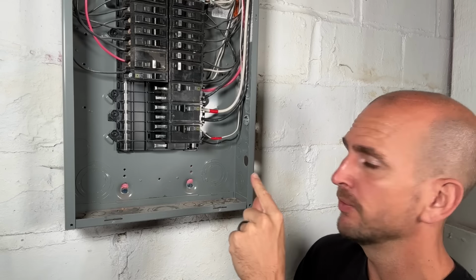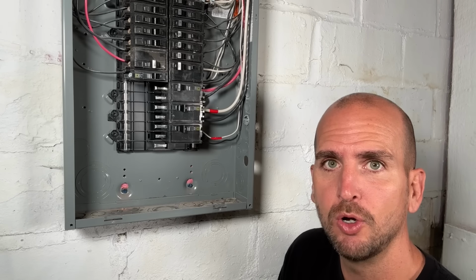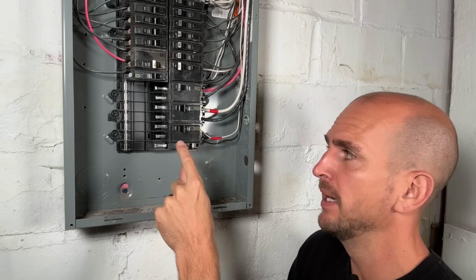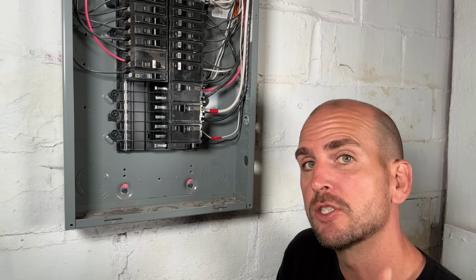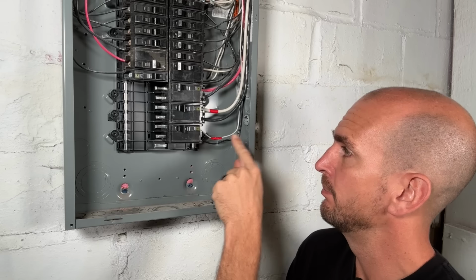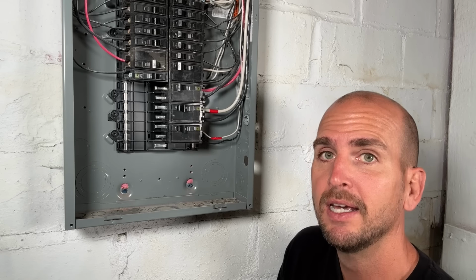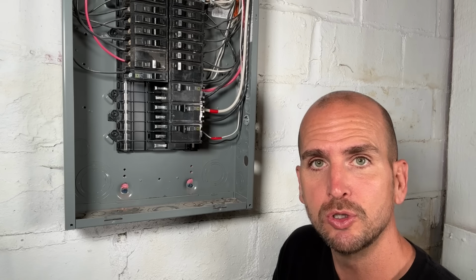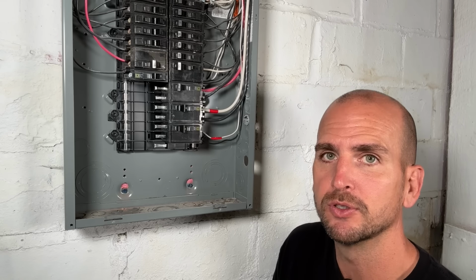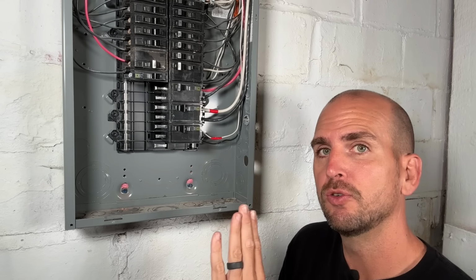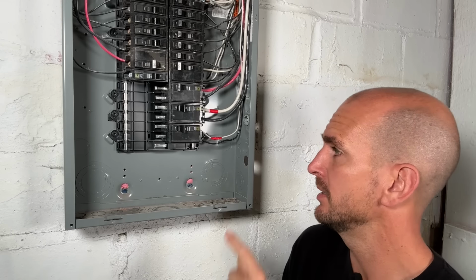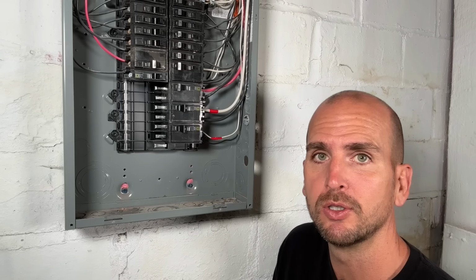And just want to reiterate, since we are using standard Romex both for our 50 amp and for our 15, that was a 2 conductor Romex. So you would have black, which is usually your hot, and white, which is usually your neutral. That would be for a 120 volt circuit. Well, in this case, it's a 240 and we needed 2 hot conductors. That's why you would mark those with red.